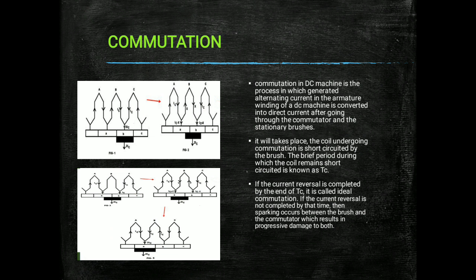There are two conductors along the brush: one on the north pole side and one on the south pole side. The direction of current is opposite in the north pole and south pole sides. At the brush axis, the summation of two currents is obtained, which flows through the brush to the external load circuit — meaning alternating current is converted into direct current. The brief period during which the coil remains short-circuited with the brushes is known as tc, the commutation time. If the current reversal is completed by the end of tc, it is called ideal commutation.